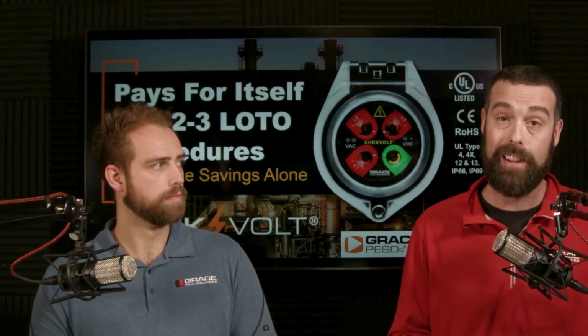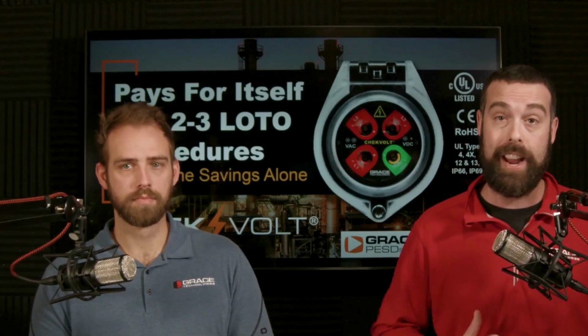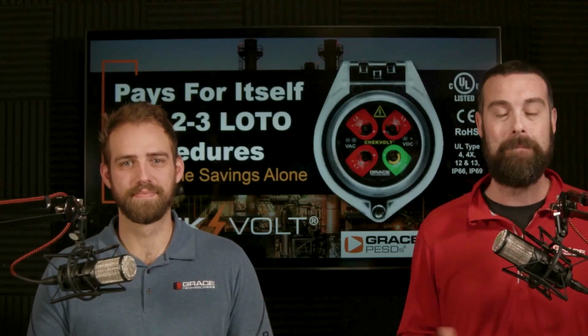What's great about the ChekVolt device - anyone with some exposure to Grace probably recognizes what are called voltage lights, or pucks, or presence of voltage indicators, or contact test points. The ChekVolt combines the technology of not only our voltage indicator, but also our contact test points. So it's a 2-in-1 device. It's also UL listed, carries an ingress protection rating of IP69, and is built with a potted construction and current limiting resistors.